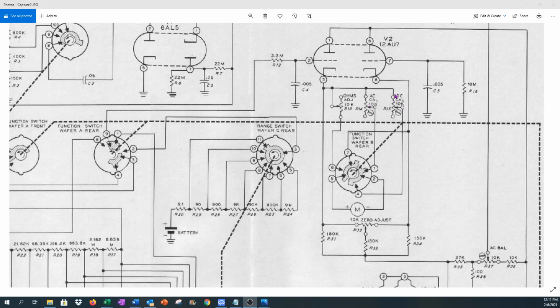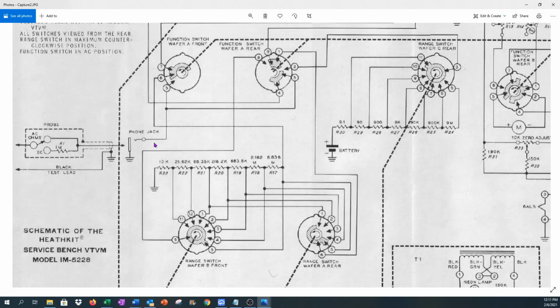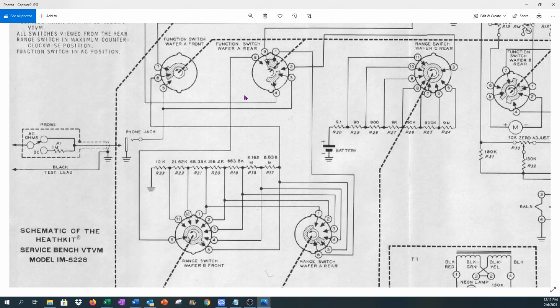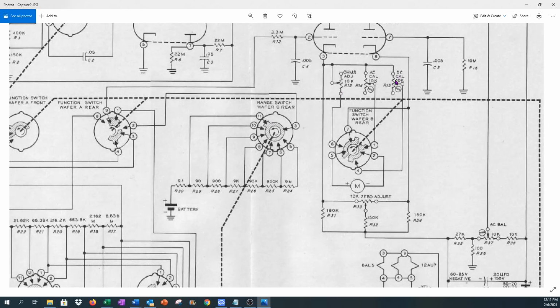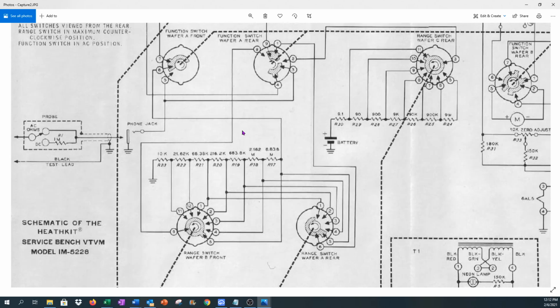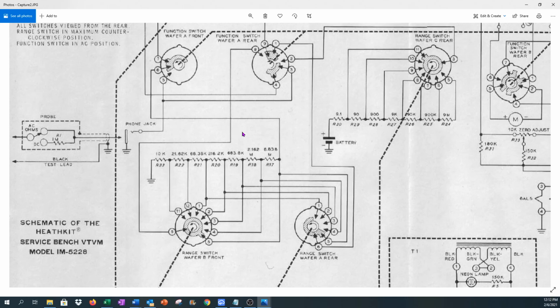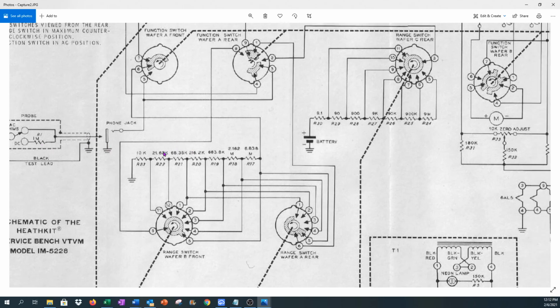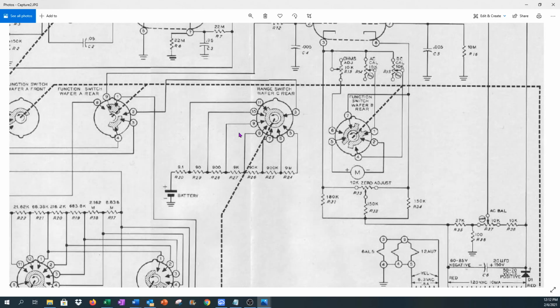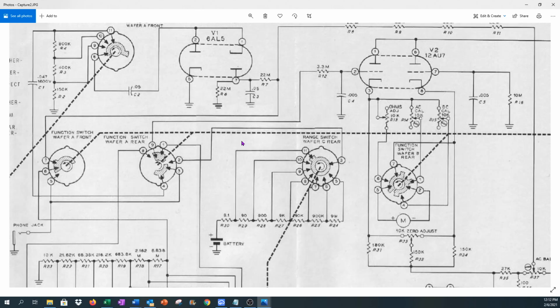Now, pretty much the AC circuit, once it gets to this point, uses the same circuit as the DC. However, in the DC cal, you have the 1 megohm resistor in the probe, right? So that's going to be a change. You don't have that in the AC. So you have this 1 meg resistor right here. So this really needs to be calibrated with that probe, with the 1 meg resistor. Otherwise, you're going to be all out of calibration. So it needs to be switched in when you do that calibration. And we're going to go through that when we actually do the calibration of this meter. But that's kind of the short and skinny of this thing.